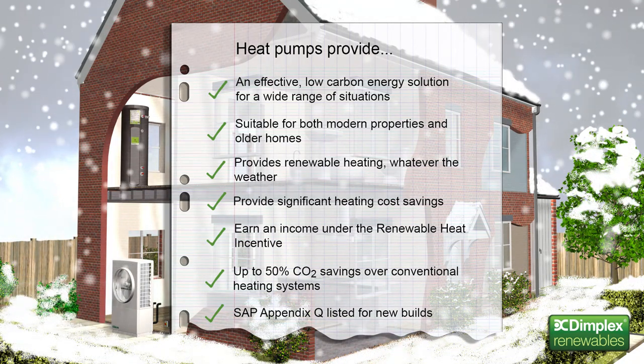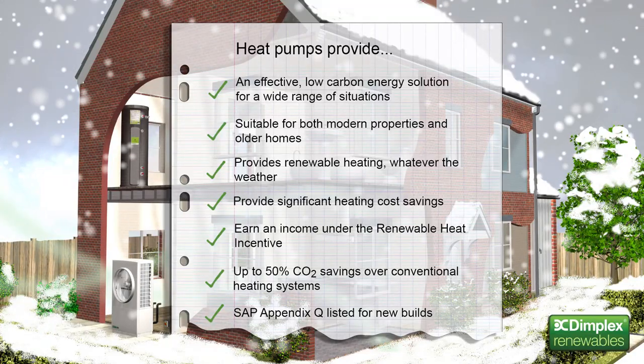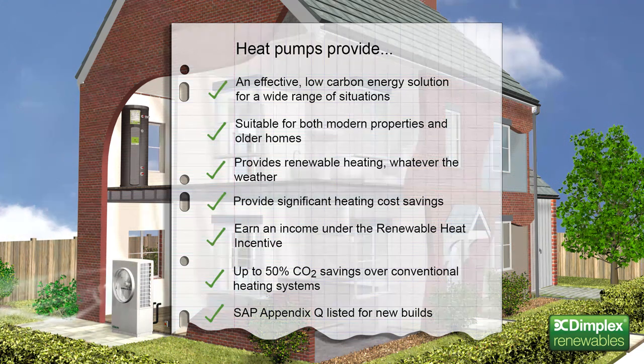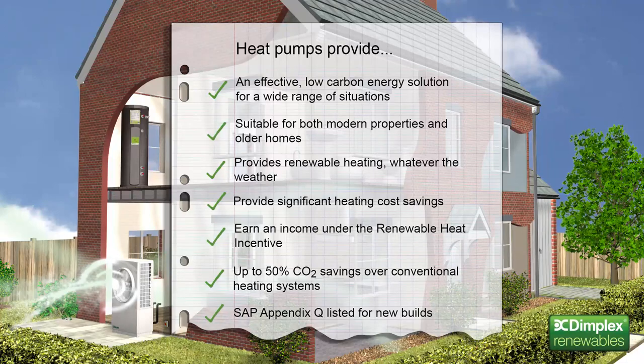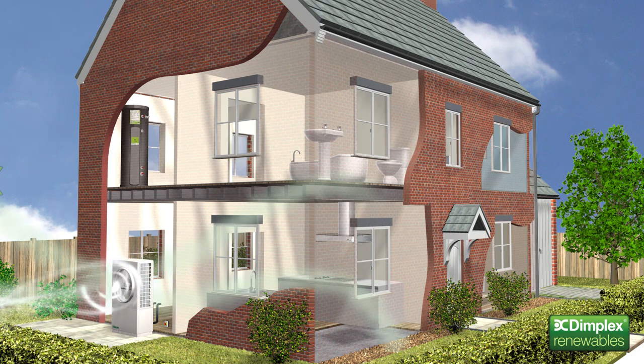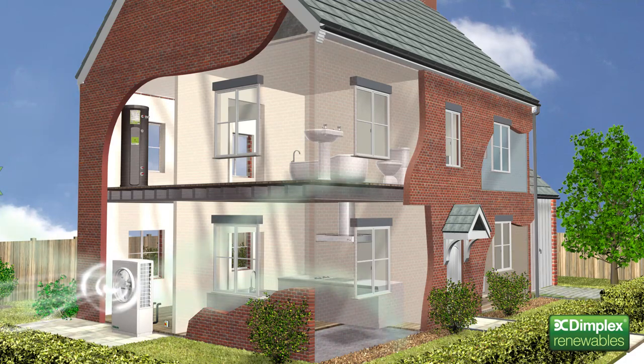Dimplex A-Class heat pumps can easily be used as a complete replacement for a conventional boiler system. With their ability to deliver fully rated output at air temperatures as low as minus 7 degrees, they make the ideal MCS 3005 compliant solution, even where heat loads of up to 16 kilowatts are required. And for larger homes with higher heating demands, Dimplex has a range of options available to operate in conjunction with a conventional boiler system.